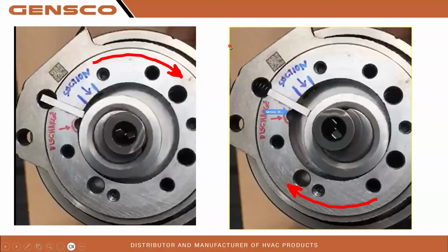This is an image of the lower compression chamber of that dual rotary compressor. You can see I have marked the discharge port. In this case, there's another plate that sits on top of this, or underneath it because this is the bottom. And it discharges through the reed valve, which you'll see a picture of shortly, into the shell of the compressor. The suction line comes in from that accumulator on the side of the unit directly into the compression chamber. In the image on the left, you can see the slide vane is recessed and pushed by the roller into its recess, which has a spring on the back side. You can see in the other slide on the other side of the page.